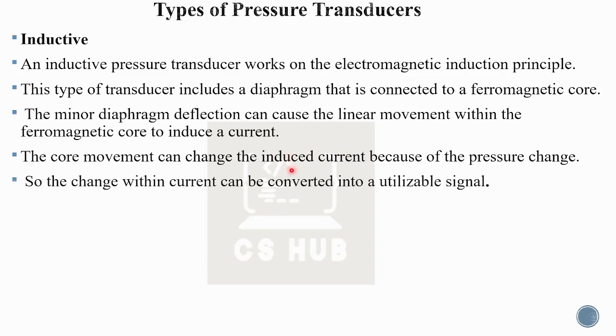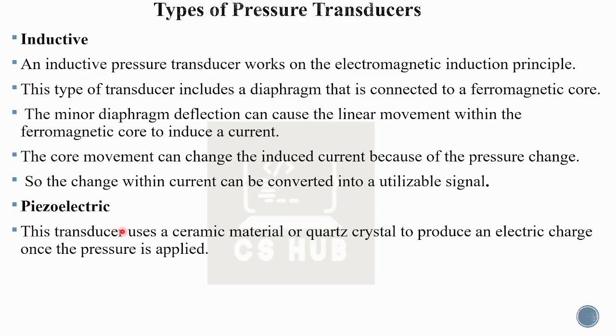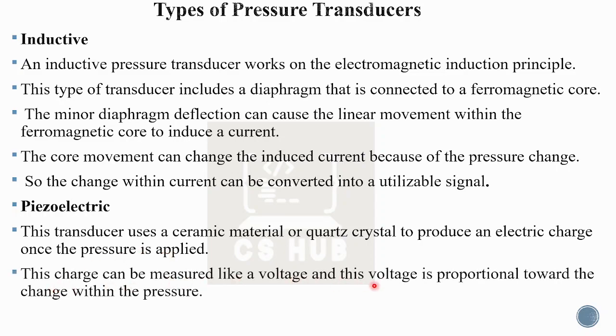The last type is piezoelectric. Piezoelectric transducers are based on the piezoelectric effect using piezoelectric crystals. When pressure is applied to the crystals, deformation occurs and an electrical signal is produced — a voltage difference is created. This transducer uses a ceramic material or quartz. Quartz is a crystal that, because of the piezoelectric effect, produces an electric charge once pressure is applied. This charge can be measured as a voltage, and this voltage is proportional to the change in the applied pressure.